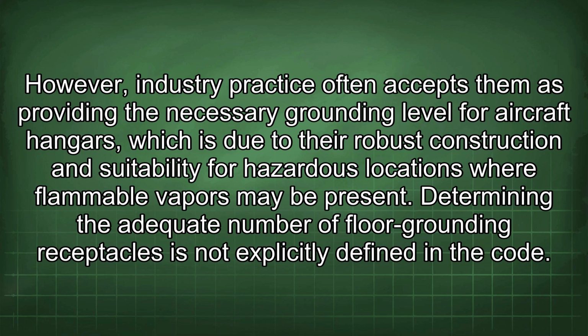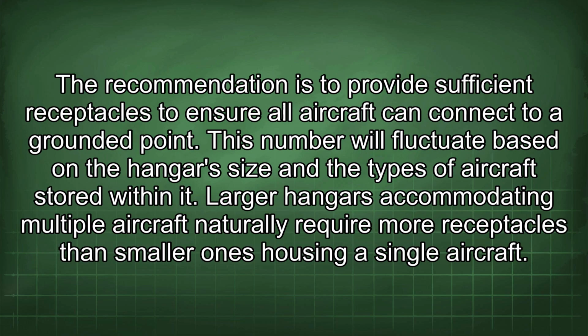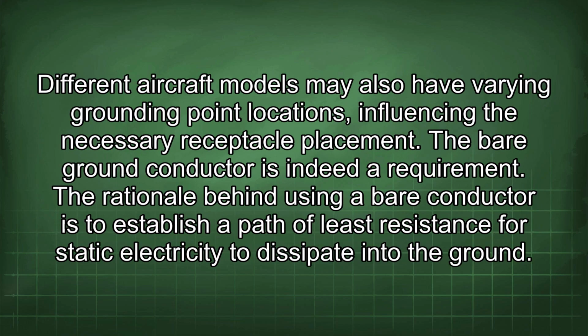Determining the adequate number of floor grounding receptacles is not explicitly defined in the code. The recommendation is to provide sufficient receptacles to ensure all aircraft can connect to a grounded point. This number will fluctuate based on the hangar size and the types of aircraft stored within it. Larger hangars accommodating multiple aircraft naturally require more receptacles than smaller ones housing a single aircraft. Different aircraft models may also have varying grounding point locations, influencing the necessary receptacle placement.